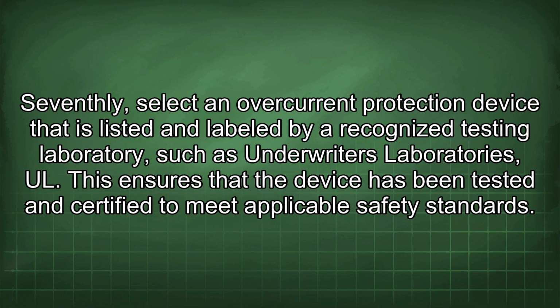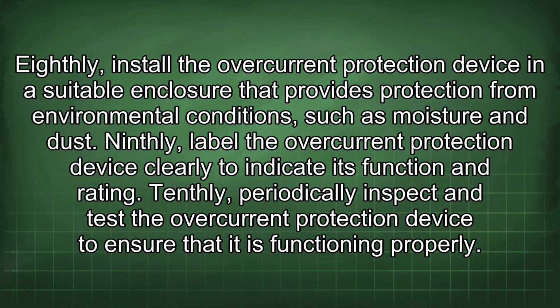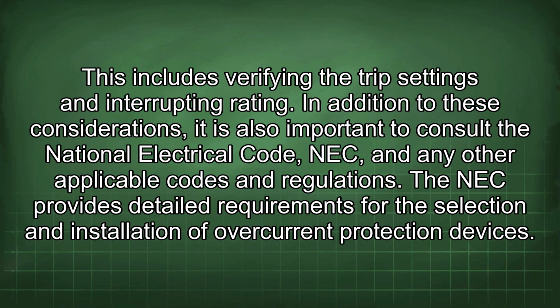Seventhly, select an overcurrent protection device that is listed and labeled by a recognized testing laboratory, such as Underwriters Laboratories. This ensures that the device has been tested and certified to meet applicable safety standards. Eighthly, install the overcurrent protection device in a suitable enclosure that provides protection from environmental conditions such as moisture and dust. Ninthly, label the overcurrent protection device clearly to indicate its function and rating. Tenthly, periodically inspect and test the overcurrent protection device to ensure that it is functioning properly. This includes verifying the trip settings and interrupting rating.